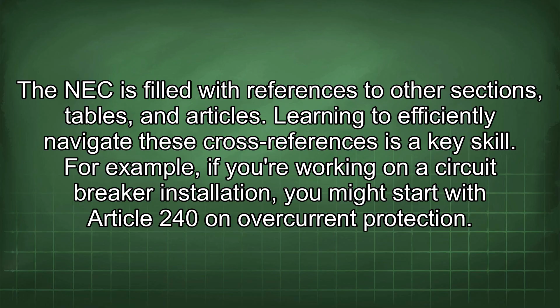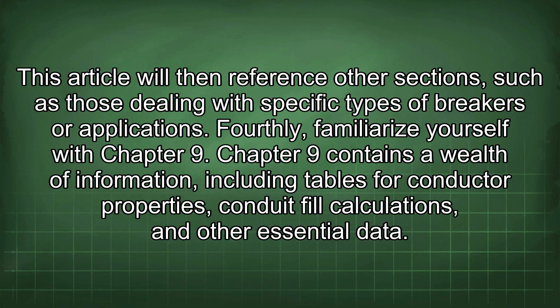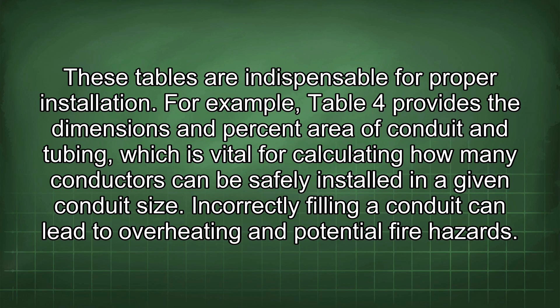Fourthly, familiarize yourself with Chapter 9. Chapter 9 contains a wealth of information, including tables for conductor properties, conduit fill calculations, and other essential data. These tables are indispensable for proper installation. For example, Table 4 provides the dimensions and percent area of conduit and tubing, which is vital for calculating how many conductors can be safely installed in a given conduit size. Incorrectly filling a conduit can lead to overheating and potential fire hazards.